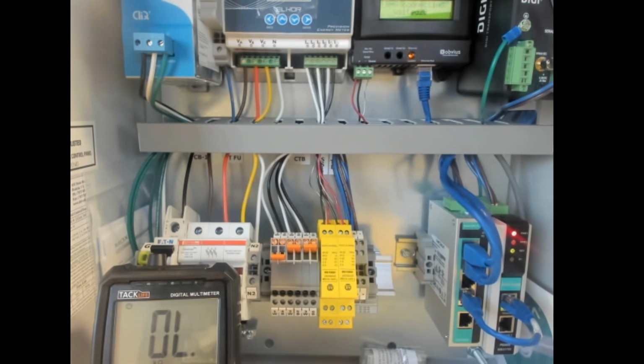The troubleshooting of them is not much different than if you were to combine some of the split core troubleshooting from a millivolt CT to a 5 amp CT. So no differences there. Rope CTs or Rogowski coils are a totally different type of measuring device, so it's got nothing to do with 5 amps. So don't worry about that.